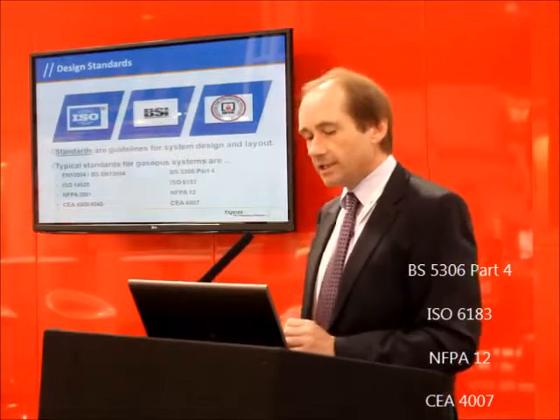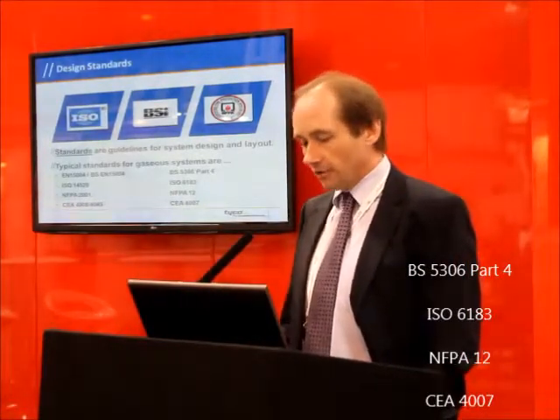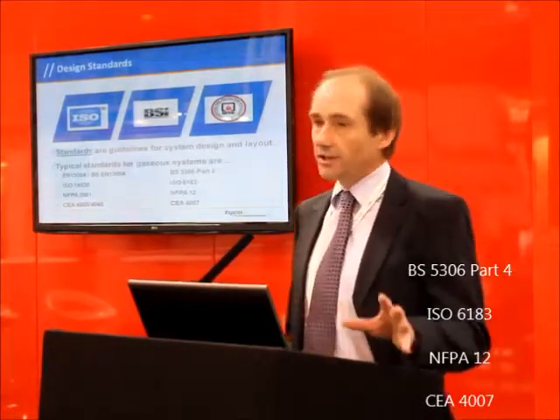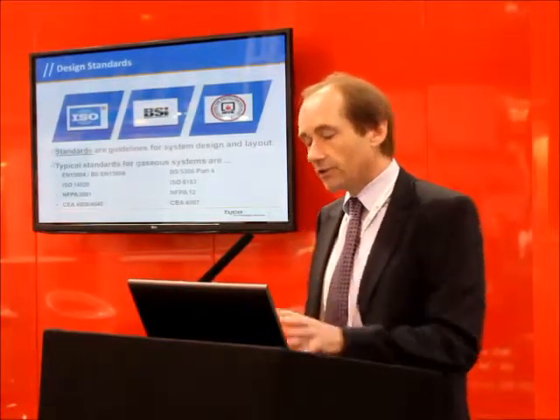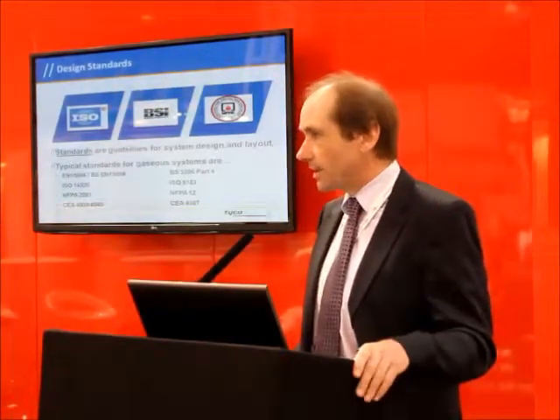The standards on the right-hand side are associated with CO2. In the UK, that's BS 5306 Part 4. There is also ISO 6183, the American standard NFPA 12 — mainly the standard of choice around the world outside the UK and some European countries — and CEA 4007, which is a CO2 standard written by the CEA, similar in nature to the clean agent standards.